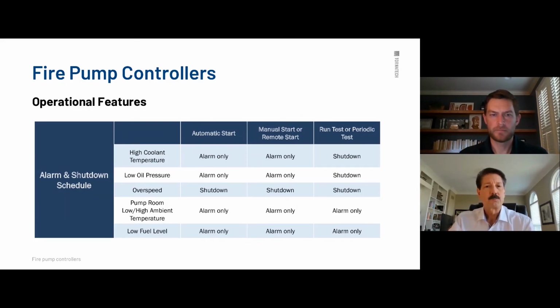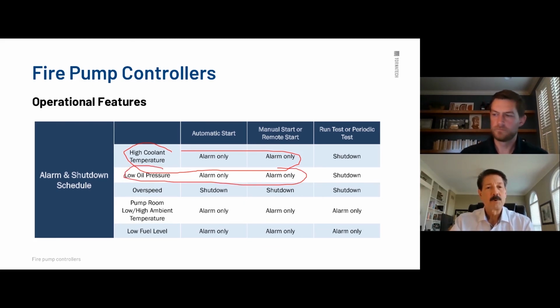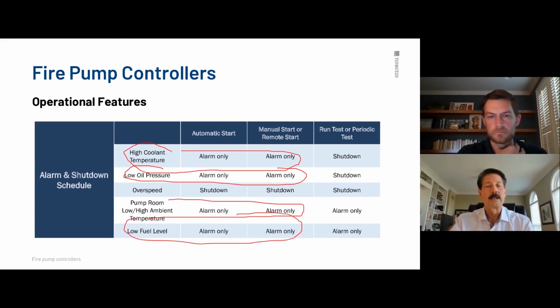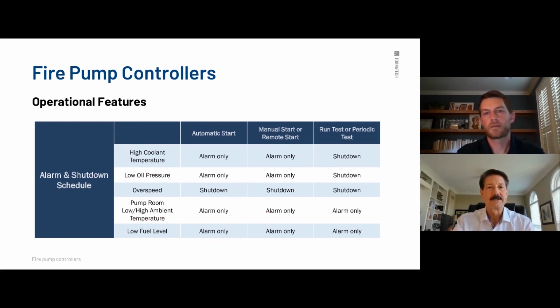Here's something I'll do really quick here. When you get into an automatic start, a manual start, or remote start, it thinks there's a potential fire. The reasoning is someone started it manually, someone remotely started, or it's an automatic. If you have high engine coolant, low oil pressure, high pump room alarm or low pump room alarm or low fuel alarm, it's only going to alarm. It will not shut it down. Why? Because it thinks there's a potential fire there. It doesn't care what happens.